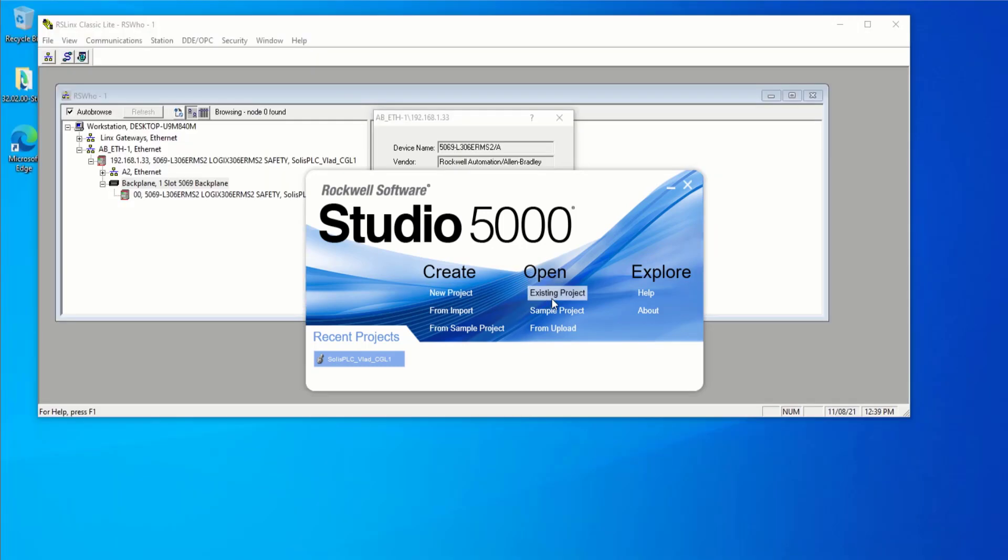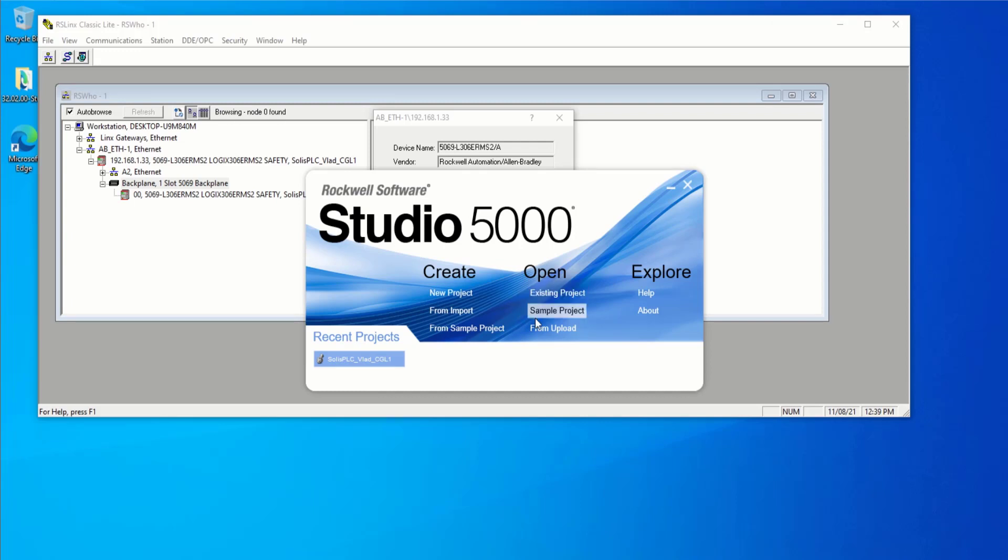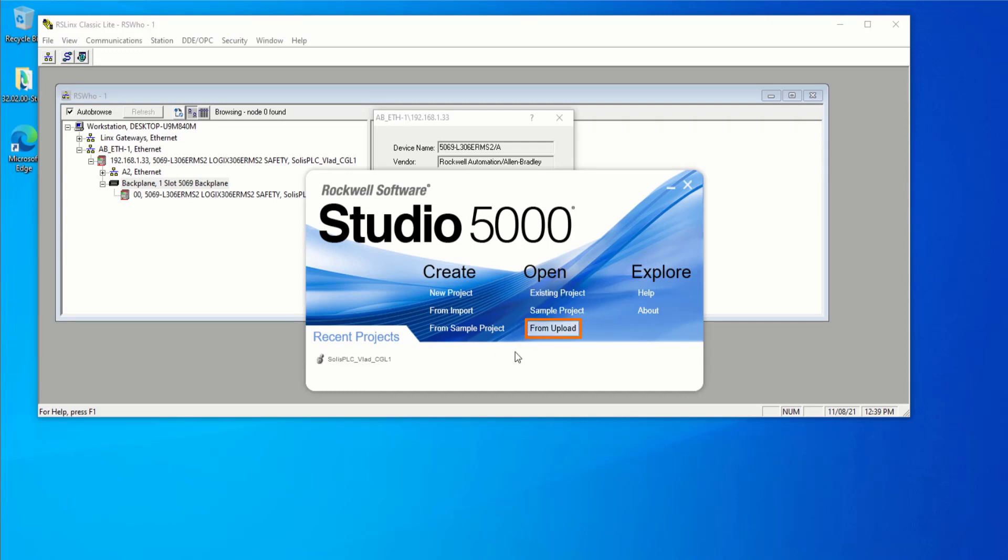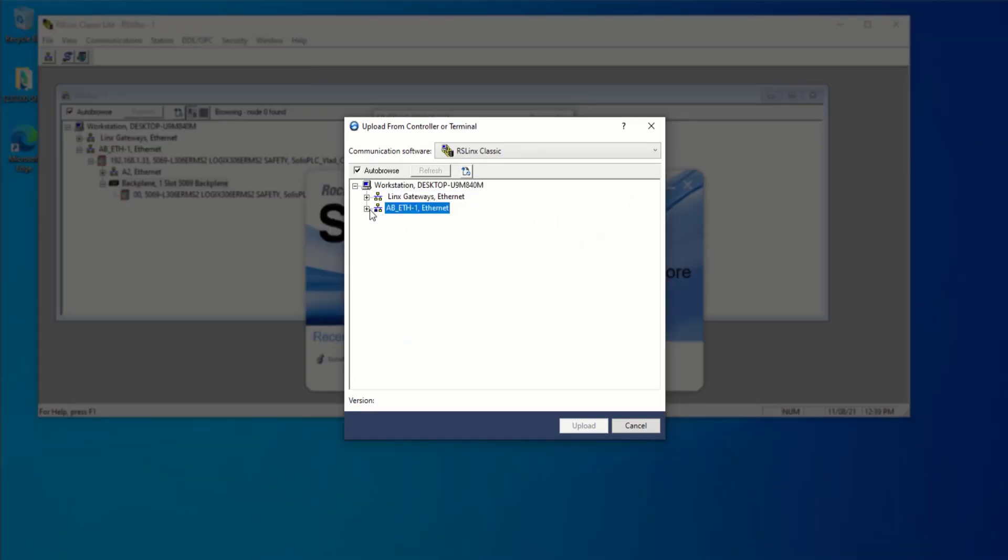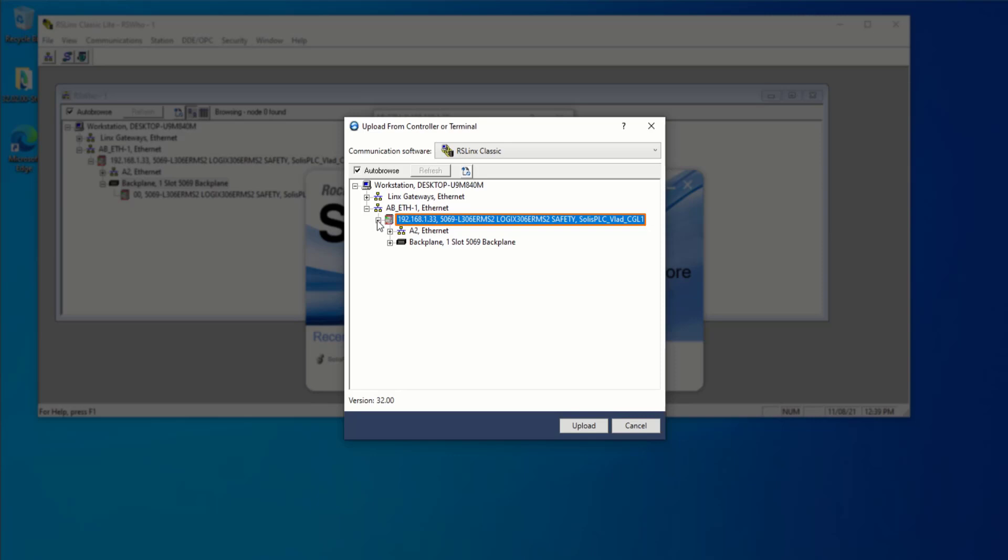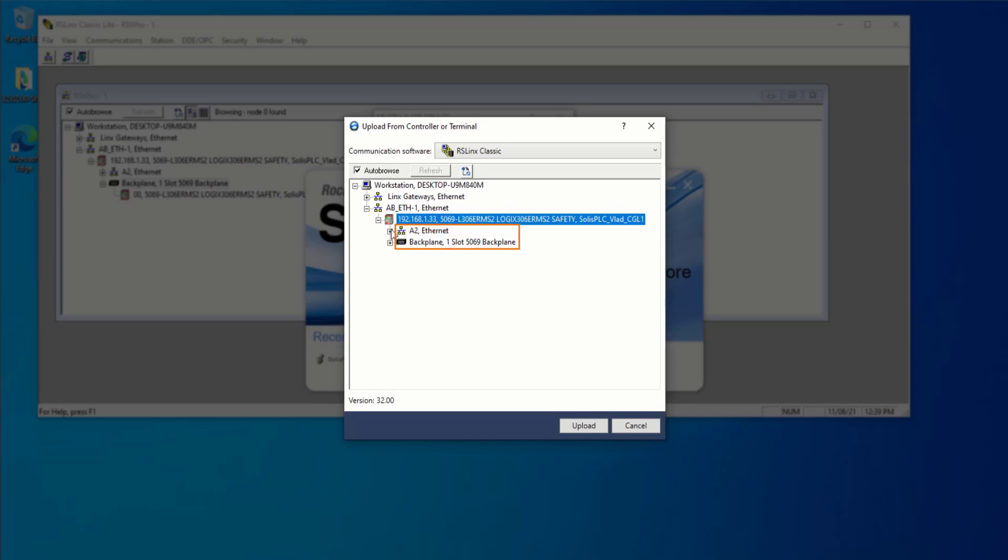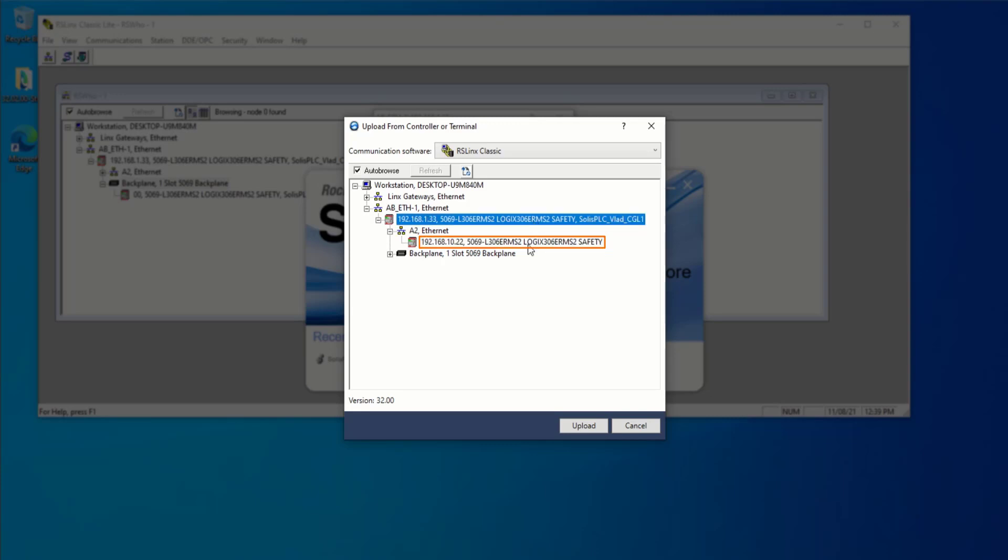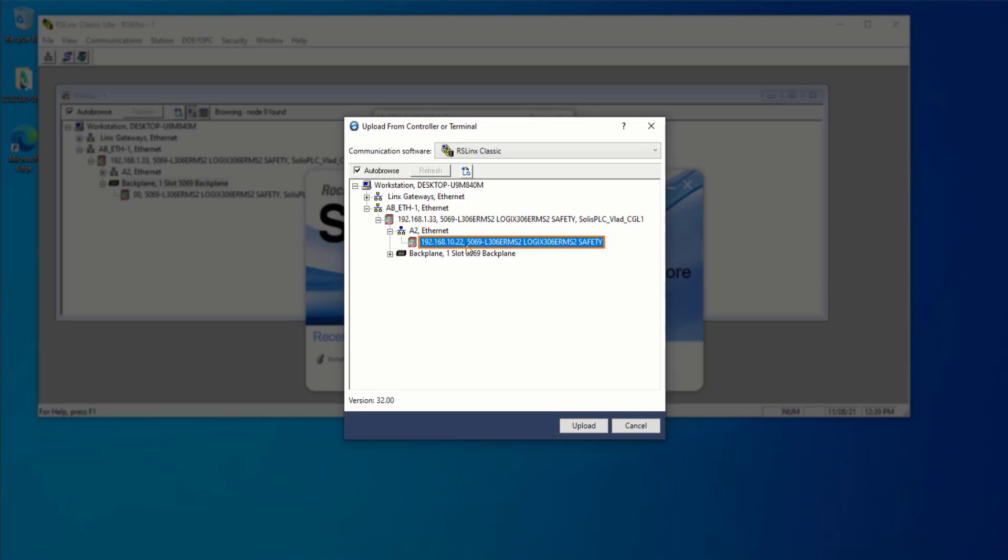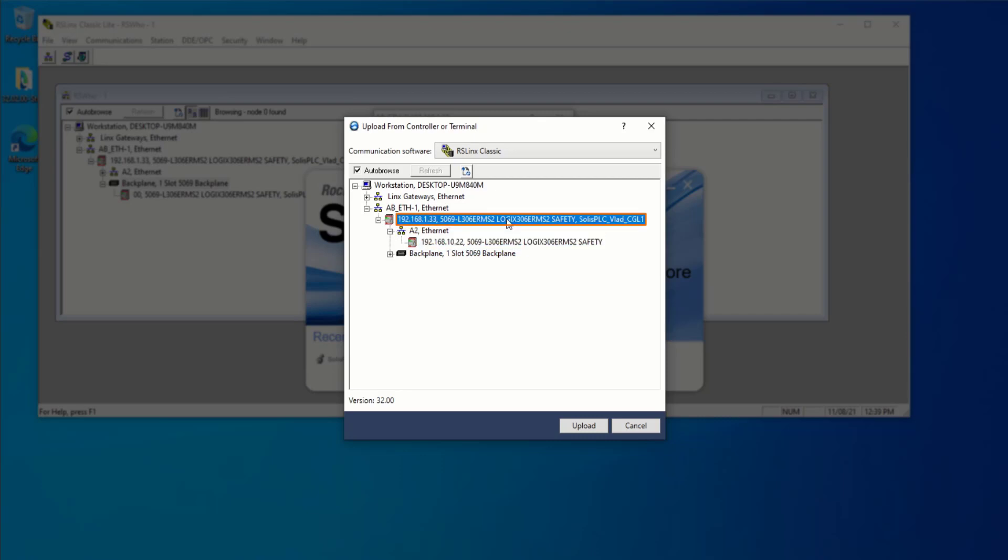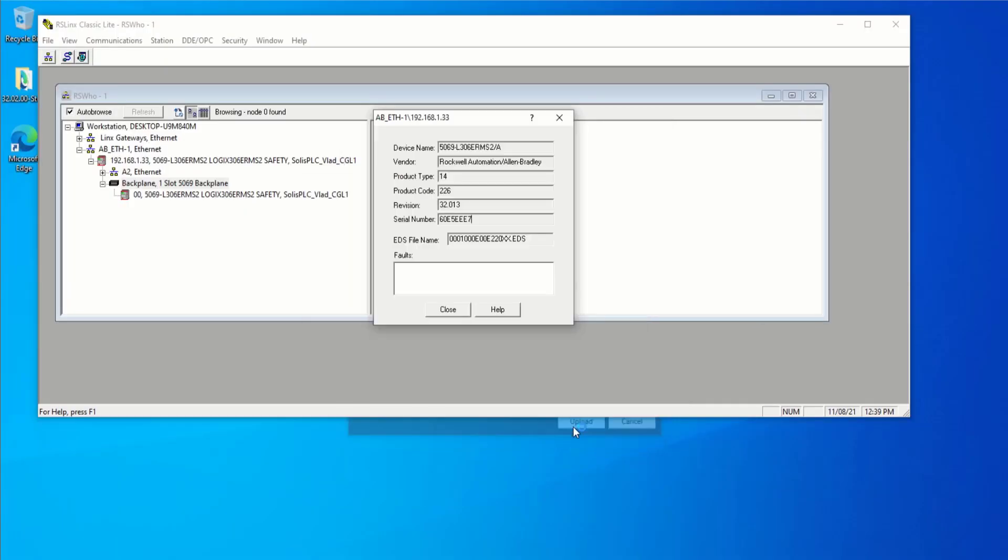So what we're going to do is, since we don't have an existing project, we're going to select from upload. So from upload, we're going to then choose the PLC from the same driver that we had in RSLinx. Expand the PLC. In certain instances, you do need to drill down and select the PLC at the lower level. And you'll notice that you can upload from the top level PLC, or you can go all the way down to this Ethernet level and then select the PLC there. There's going to be certain cases where that is going to make a difference. In this case, I don't believe so. So we're going to press on upload.